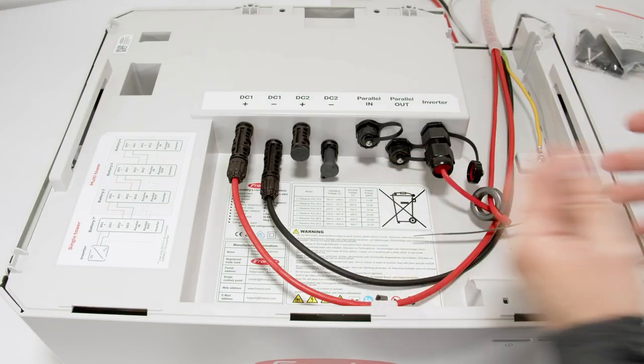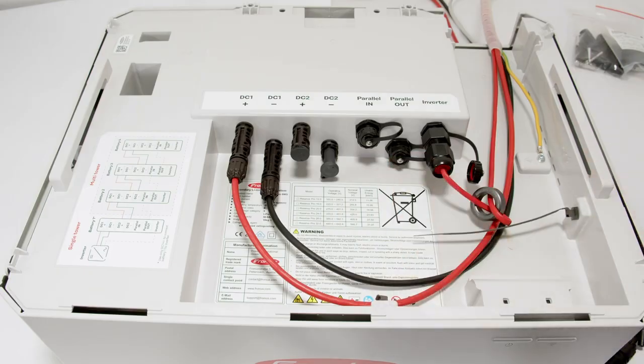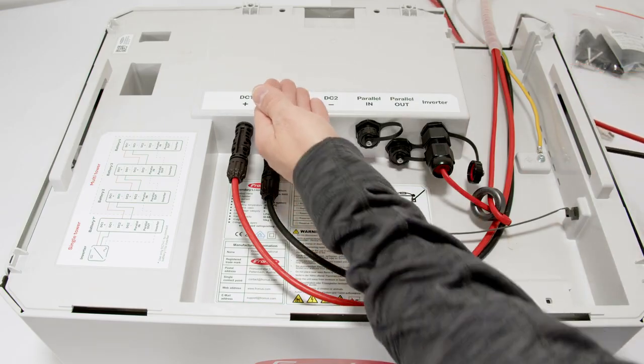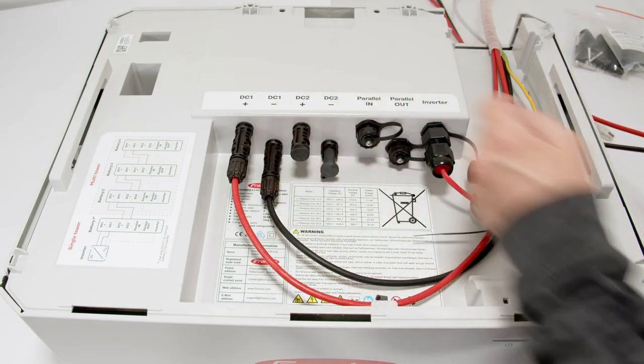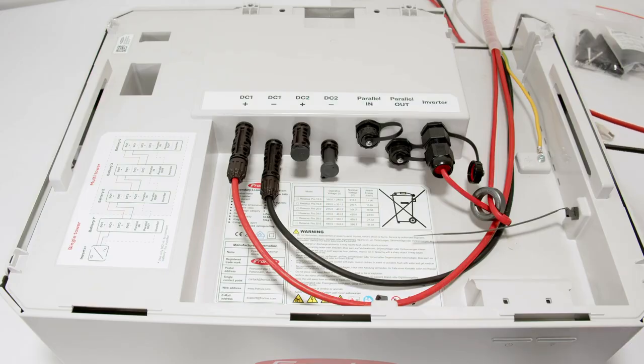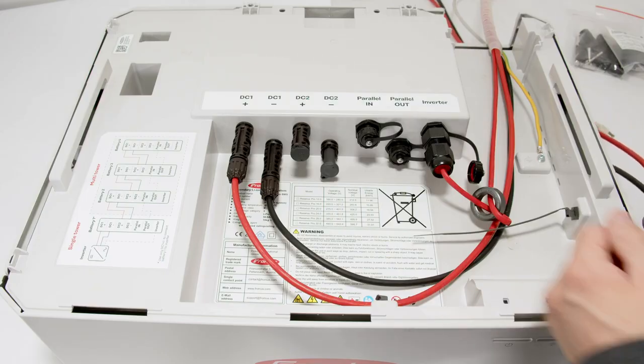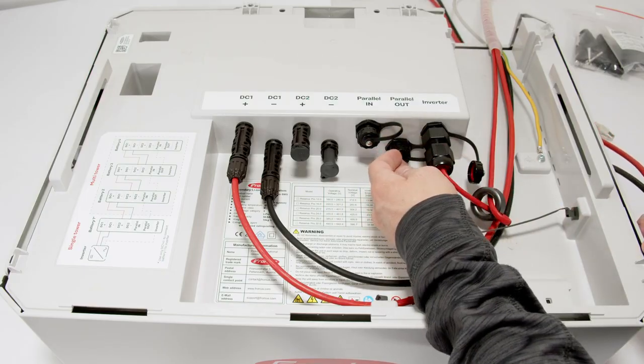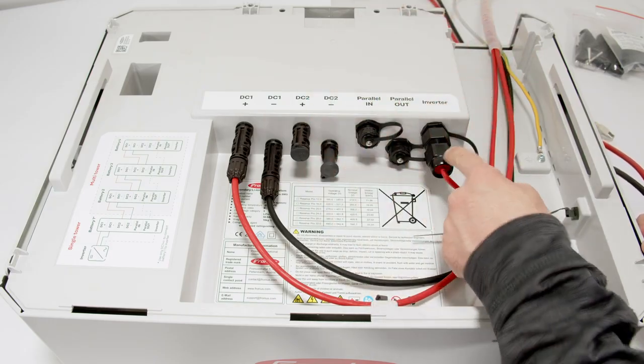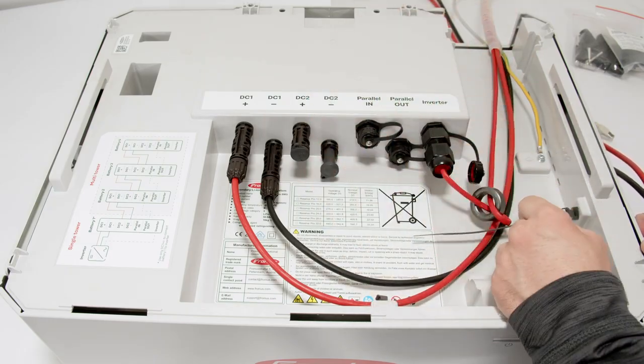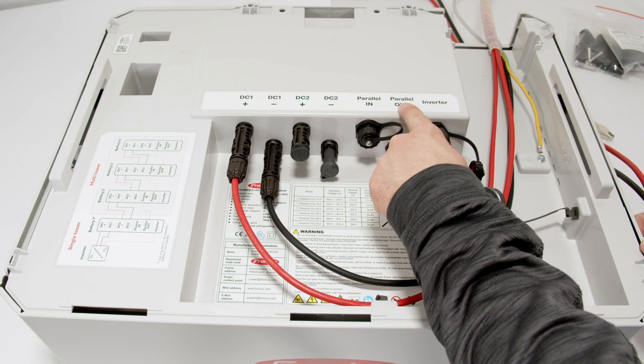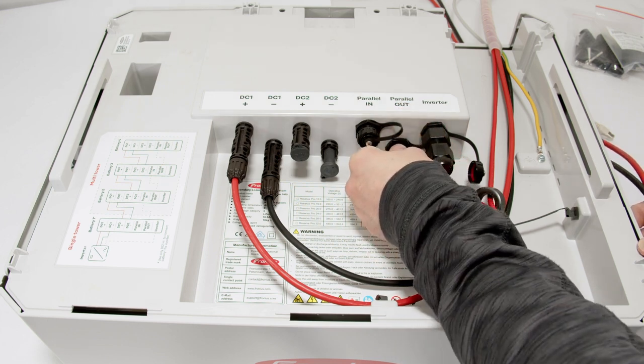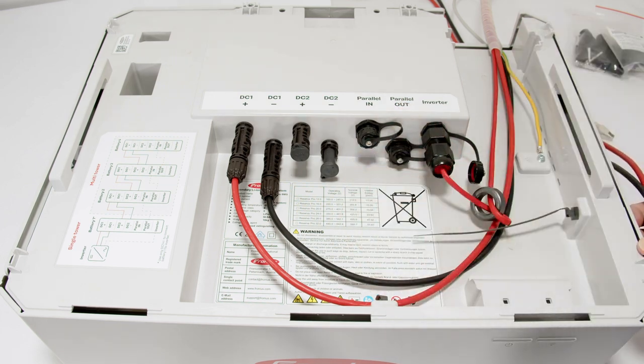After that, if you're installing multiple batteries within a system, you now need to do the parallel connection of the towers, and therefore we are using our DC2 plus and minus connectors and our parallel in and out connectors. Please note, for the parallel connection, for the data communication, you will always use for the first battery in the system, the one that is connected with the inverter, the parallel out contact to go with the first data communication cable to the second battery.